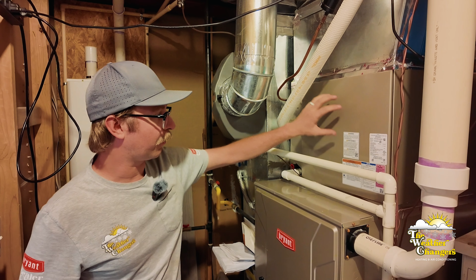let's head inside. Now we're downstairs. We're going to take a look at the coil here. This is where the refrigerant flows through. Air passes through that and it cools the air. So we want to make sure that this is clear of dirt, dust, and debris. Now we're going to use a scope to take a look at the inside. So this will let us know if this coil needs to be cleaned.